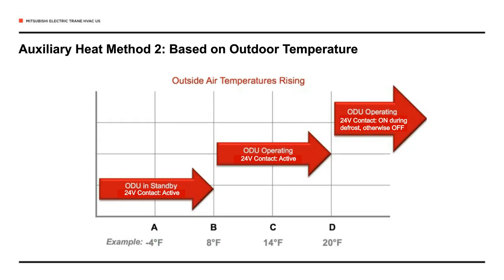When we reverse the cycle and the temperature outside is rising, we just reverse the sequence that I described before. However, we have 2 different trigger points now. Instead of triggering at points C and A as temperature is falling, we're triggering at points B and D, or in this case, 8 degrees Fahrenheit and 20 degrees Fahrenheit.